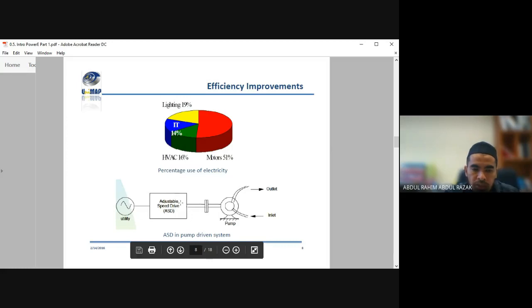Okay, here we need an adjustable speed drive, means that it can gradually speed up from 0 up to the rated speed of the pump. So adjustable, ASD, adjustable speed drive. From AC, convert to DC, and the DC is fed to the pump. So it will gradually increase. If this is a DC pump, it will gradually increase from 0 to maybe 200 volt or 300 volt that the pump needs. But if this is an AC pump, then this should be an inverter. So it will increase gradually from maybe 0 hertz to 10 hertz, 20 hertz, up to 50 hertz of the pump's required frequency.